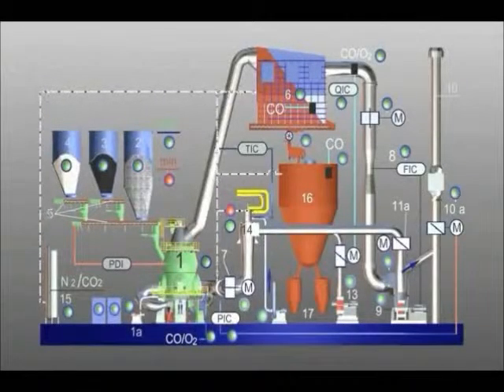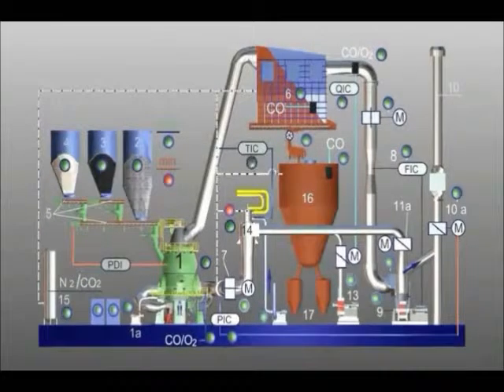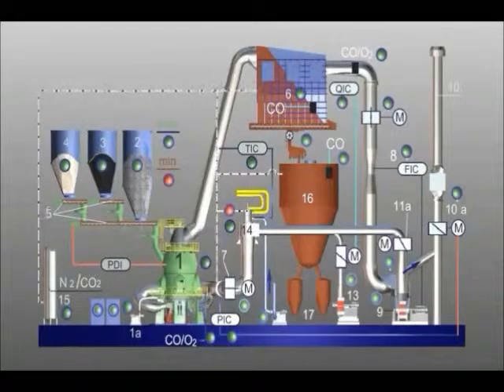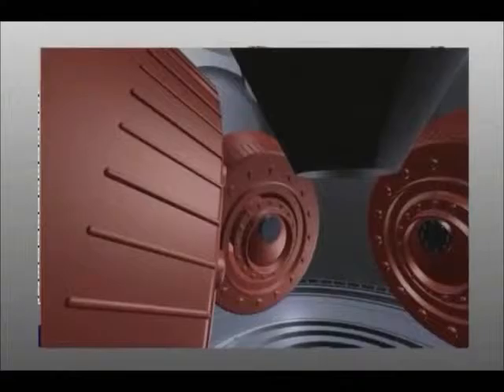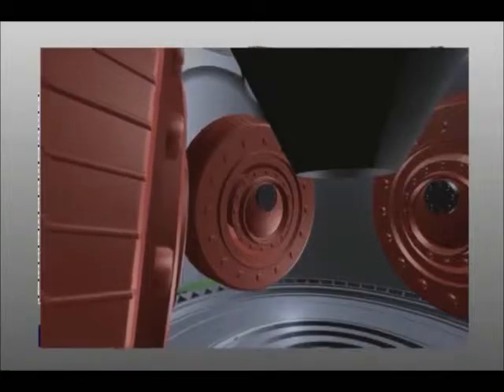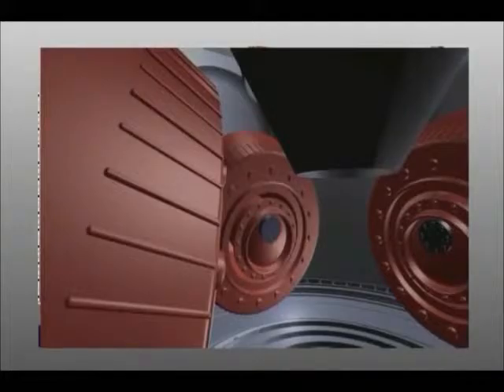The vacuum pressure after the mill continues to be regulated to a value of minus three millibar. In order for the coal feed and as a result grinding operation to be enabled, the temperature after the filter must be above 65 degrees Celsius and the oxygen content must be lower than 12 percent with moist gas. Working pressure control is active and the grinding rollers can be lowered.